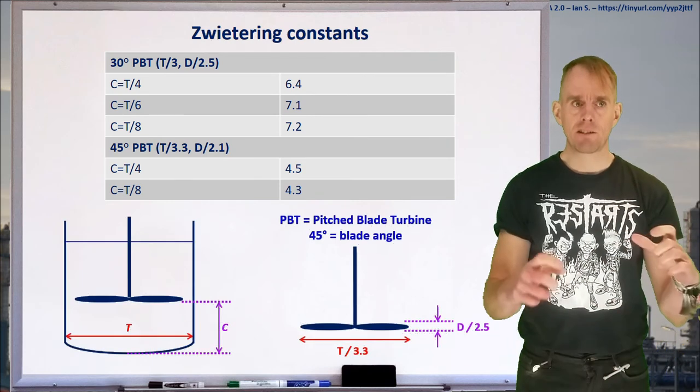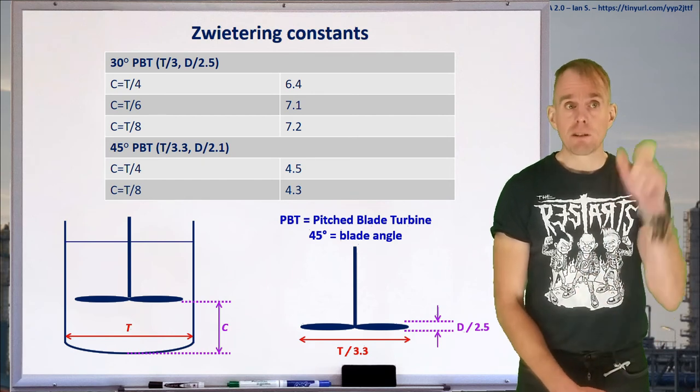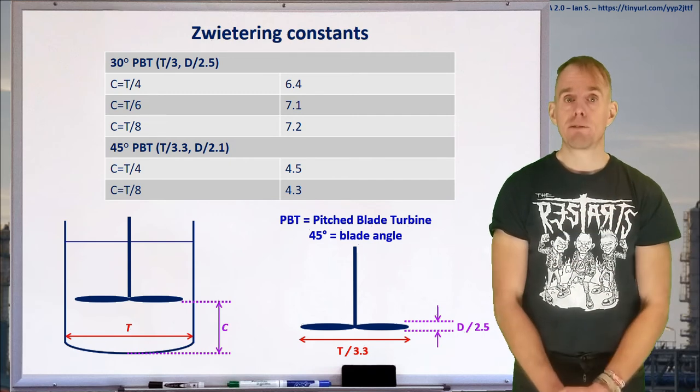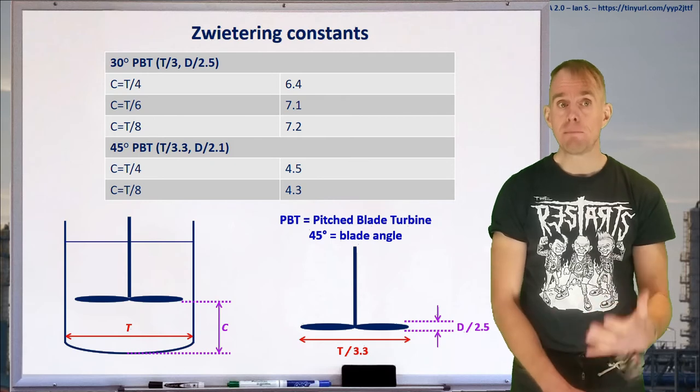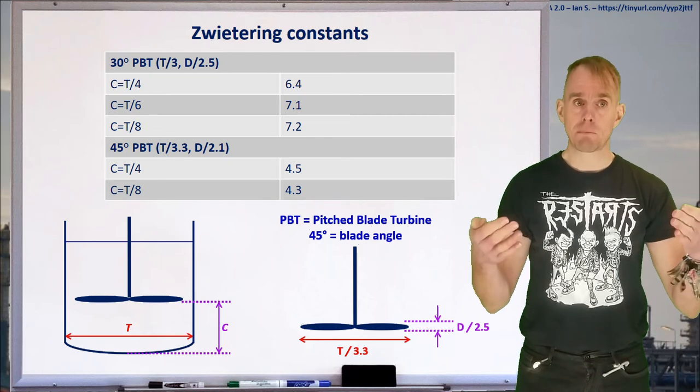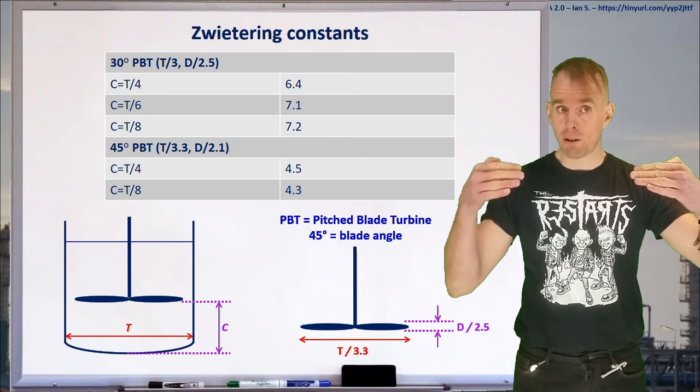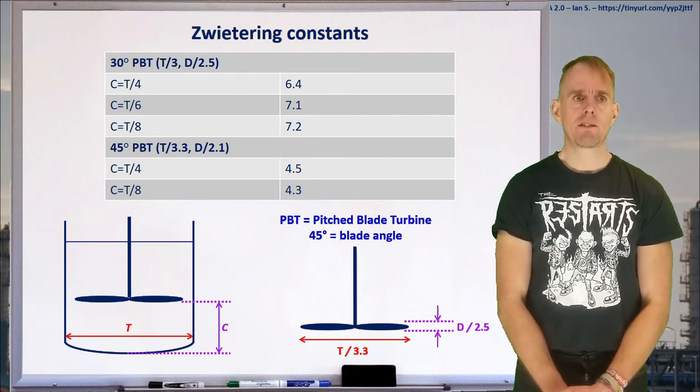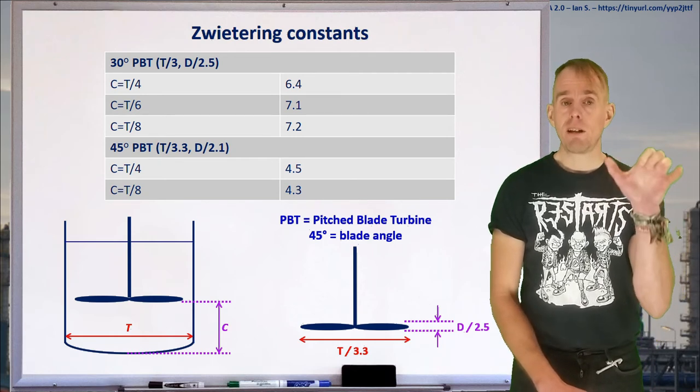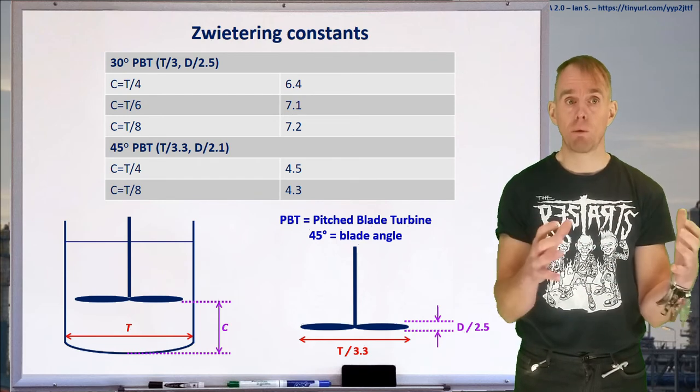Let's look at that second set of data, that is 45 degree PBT. A PBT is a pitched blade turbine. So these three-letter acronyms that follow the blade angle refers to what kind of impeller design you're dealing with. And PBT, our pitched blade turbine, is a very common one to use. And we can see in this table now we've got a pitched blade turbine with blades angled at 30 degrees to the horizontal and 45 degrees to the horizontal. OK, so let's look at T over 3.3. Well, T is our tank diameter. T over 3.3 is our impeller diameter. So it's 3.3 times smaller than our tank.